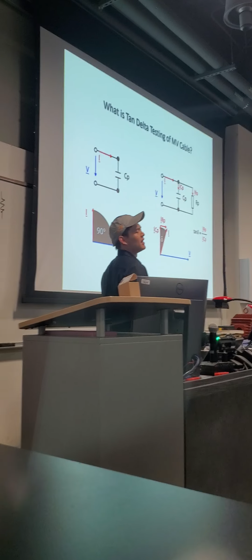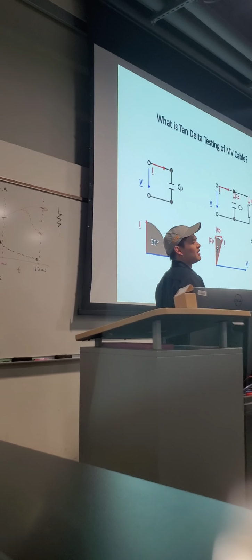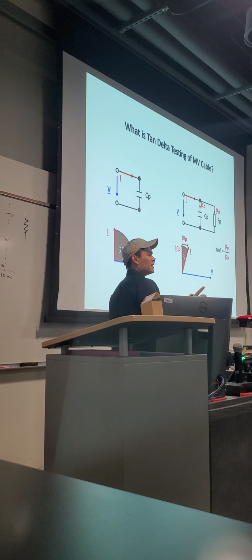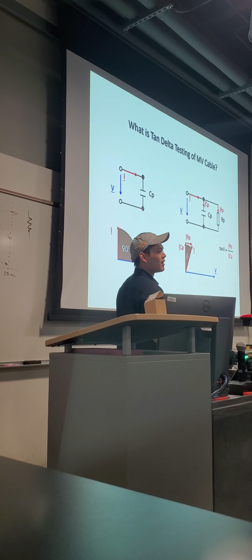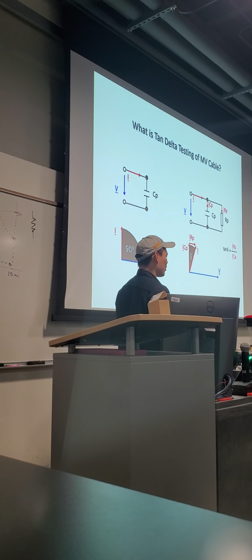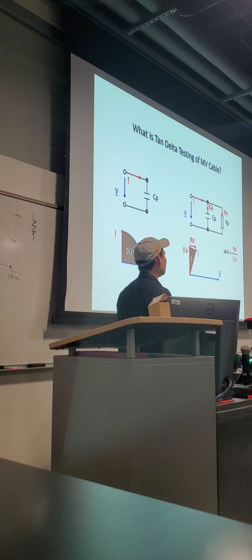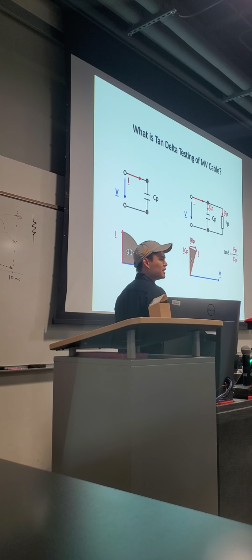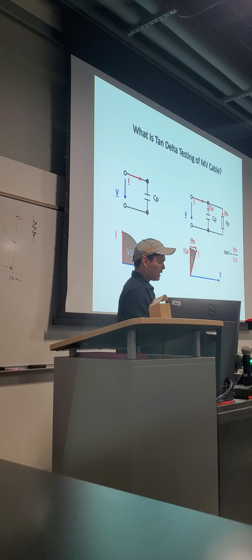Earlier you had mentioned PD is not part of VLF testing or tan delta. So in this case, it will not be a part of it. PD is usually performed at power frequency because that's what the system actually sees. For VLF testing, I'll give you two examples. One will be your tan delta, but the other VLF test will actually be a VLF high pot.